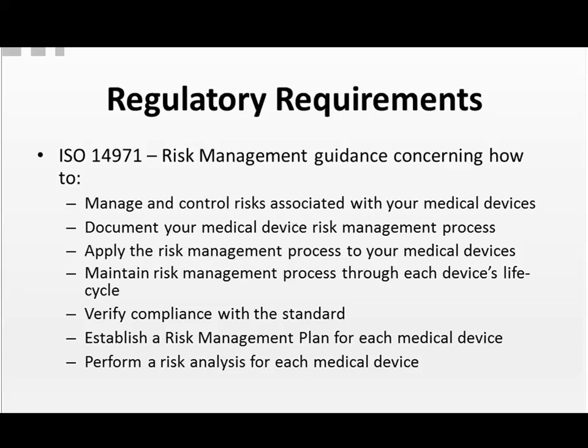Now, along with all international performance standards, ISO 14971 is subject to periodic review and update. These revisions are adopted by various countries, but not always at the same time or in the same way. When ISO 14971 is used to meet regulatory requirements, the version to comply with may differ depending on the regulatory regime and potentially the type of medical device that you're hoping to field. It's important to determine which version you must comply with.